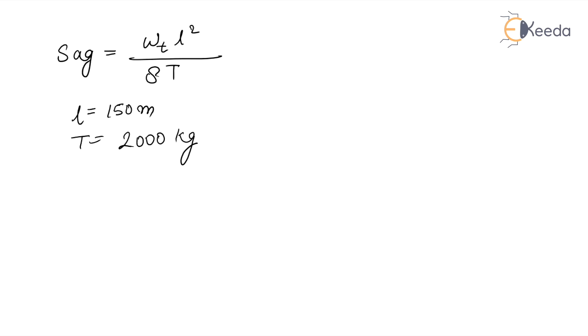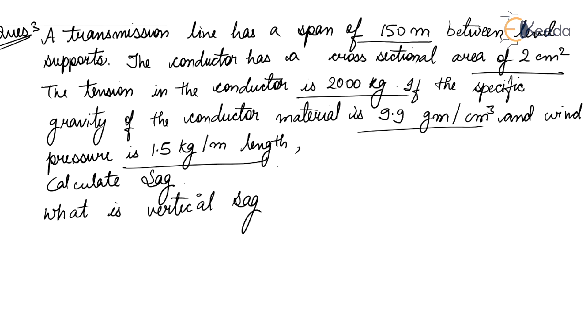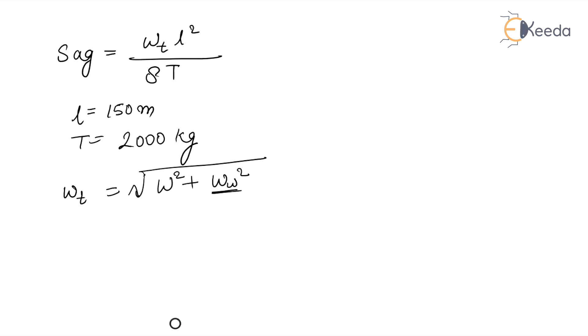We have to find out the total weight of the conductor, WT. The total weight per meter length of conductor is equal to √(W² + WW²). WW is the wind force or wind pressure, which is given as 1.5 kg per meter, so WW = 1.5 kg/m.